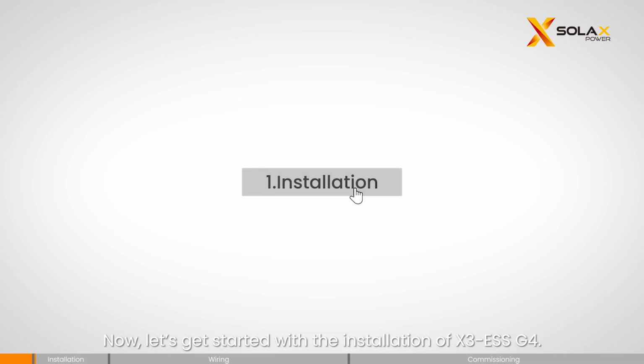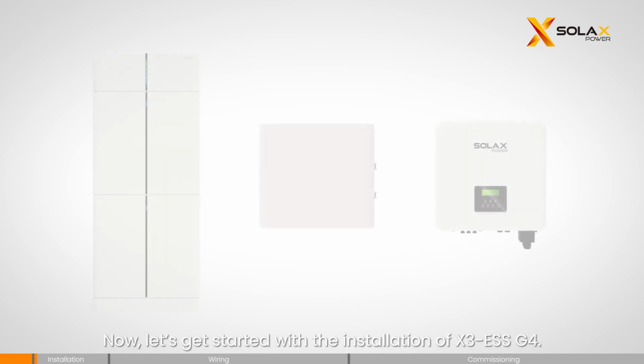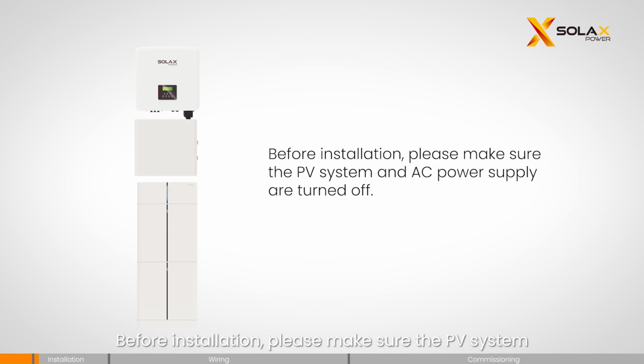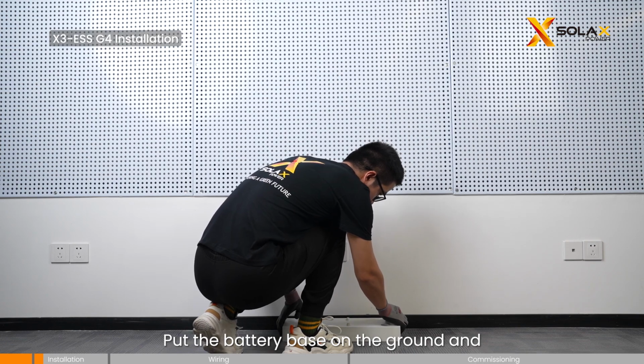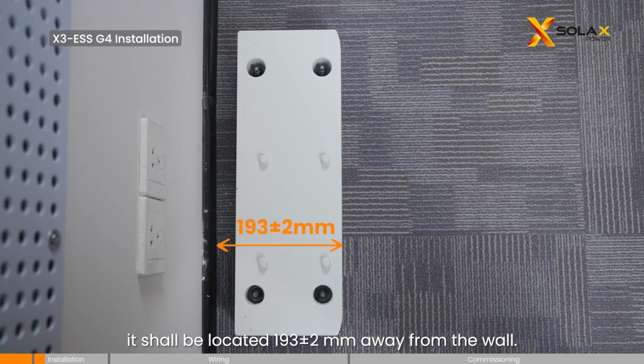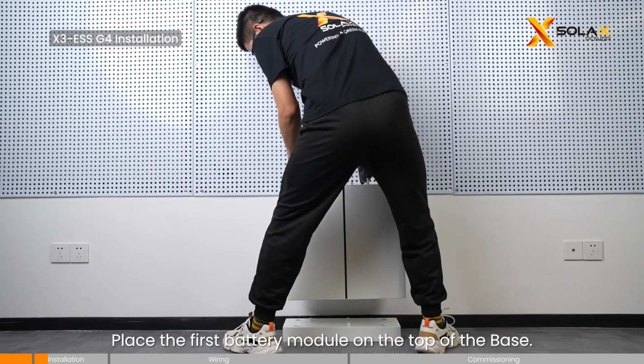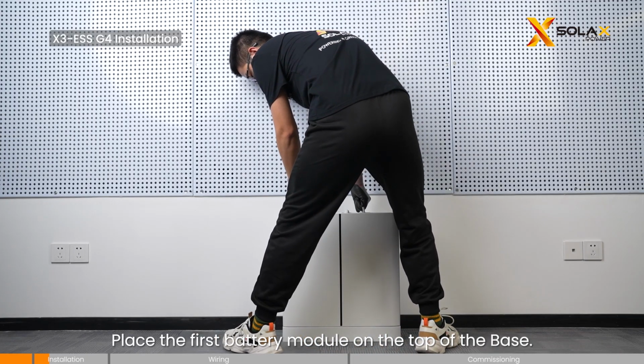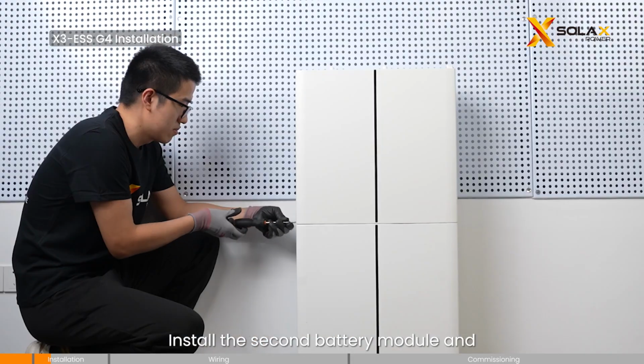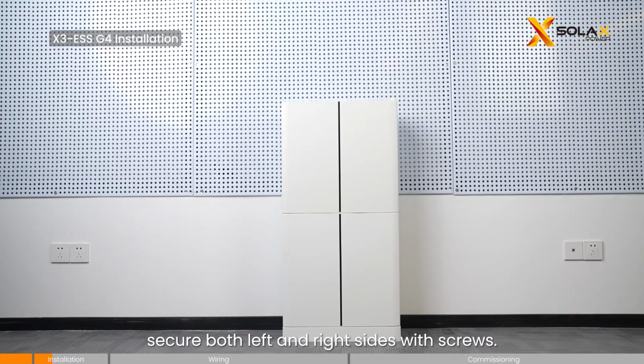Now, let's get started with the installation of X3-ESS G4. Before installation, please make sure the PV system and AC power supply are turned off. Put the battery base on the ground and it shall be located 193 plus or minus 2 mm away from the wall. Place the first battery module on the top of the base. Install the second battery module and secure both left and right sides with screws.